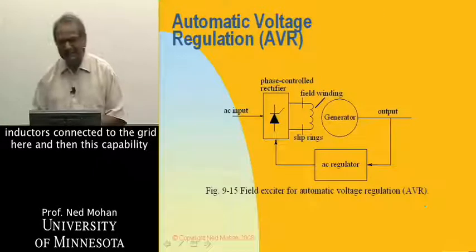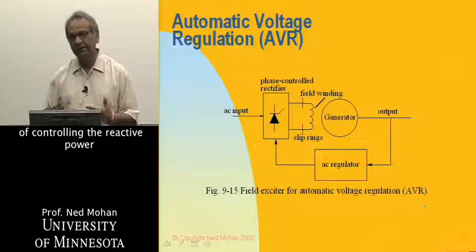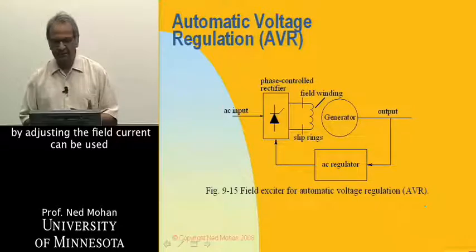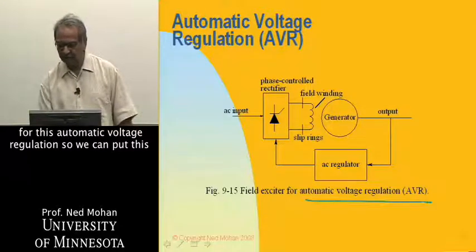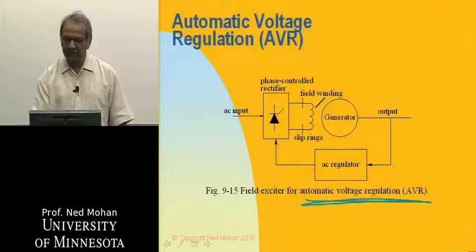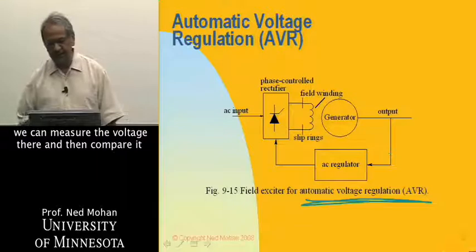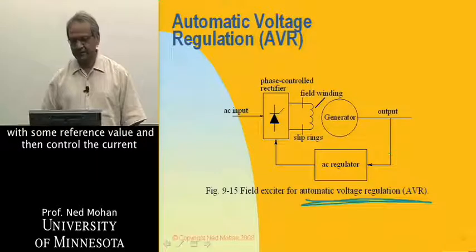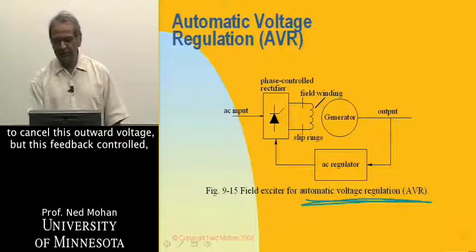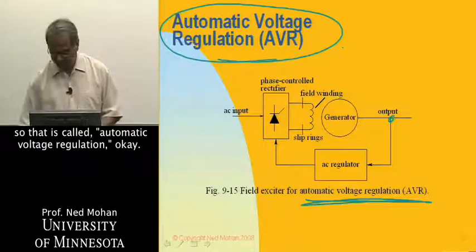This capability of controlling reactive power by adjusting the field current can be used for automatic voltage regulation. We put this in a feedback loop: wherever we want to keep a bus voltage constant, we measure the voltage there, compare it with a reference value, and control the current into the field winding to regulate the output voltage. That is called automatic voltage regulation.